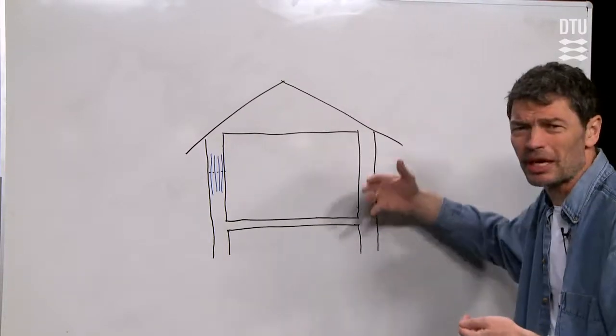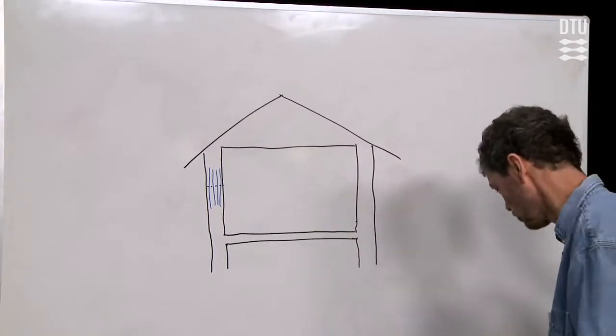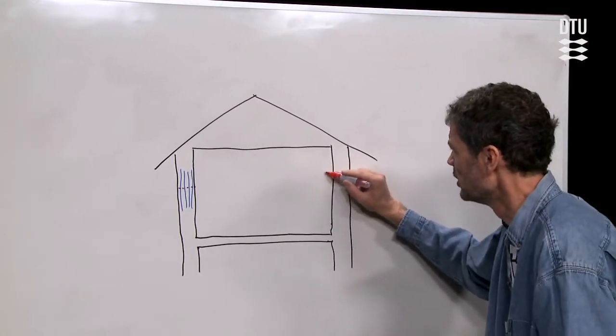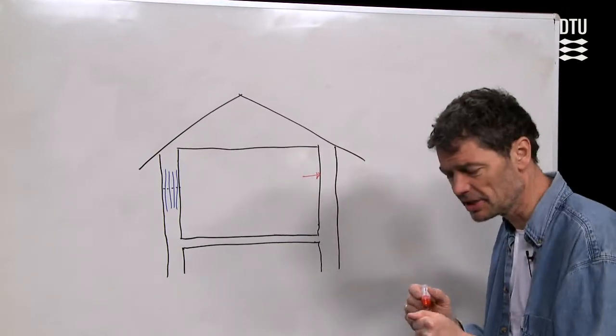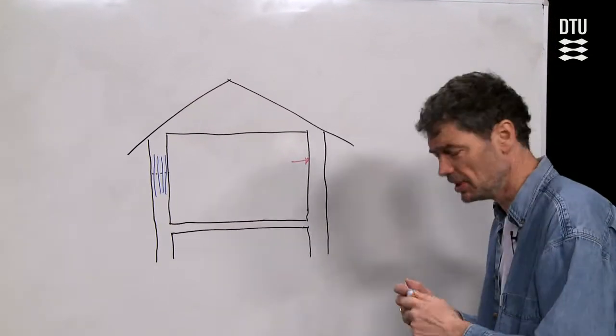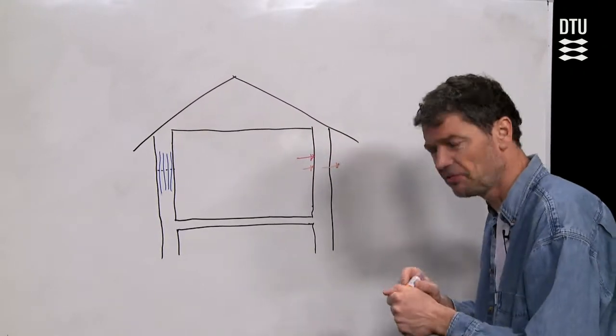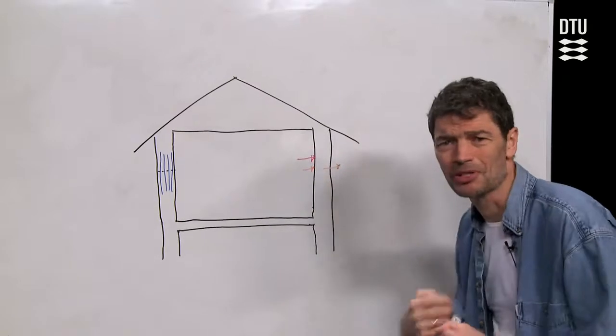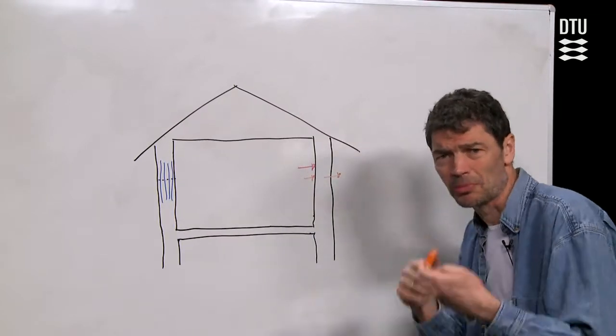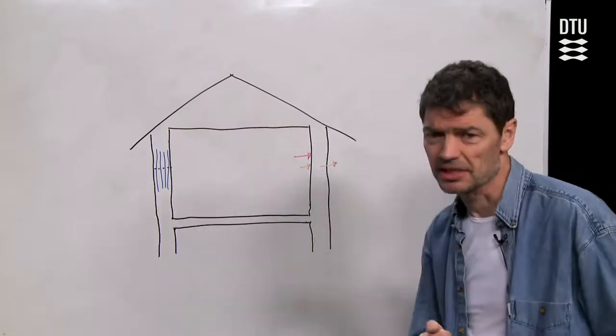We can use analytical theory for a wall of a certain thickness, where if the wall is exposed to some temperature impulse on one of the sides of the wall, then we can see what is the result of the heat that flows into the wall and what flows out of the wall. Analytical theory covers everything what happens within the wall. But we are going to use some response factors for those impacts and the responses in terms of temperature impacts and heat flow results as those responses.